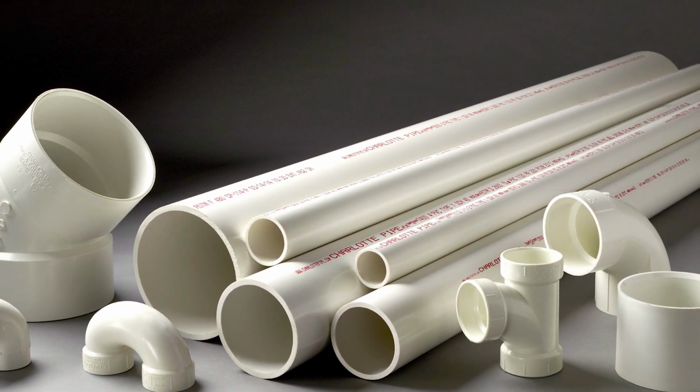Yes. So PVC is going to be our most restricted pipe because of the temperature ratings that it can handle. So you're not going to use PVC inside of a home at all on a domestic water system. Other than that, PEX, copper, CPVC even are all approved piping for water systems. Okay. So in a home, you can use anything on the table but PVC and then the black steel pipe. Copper, CPVC, PEX are all approved for domestic water systems by codes in all jurisdictions around here.